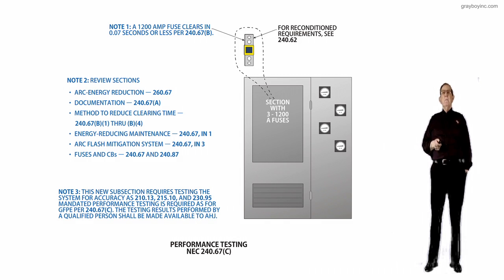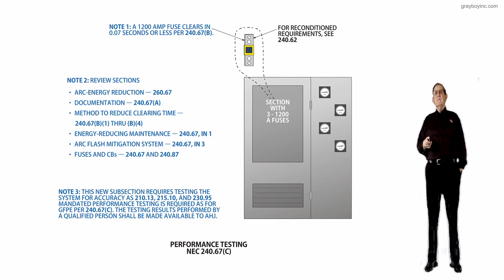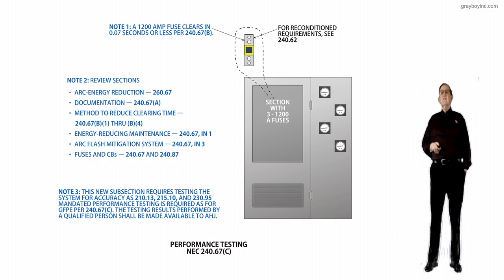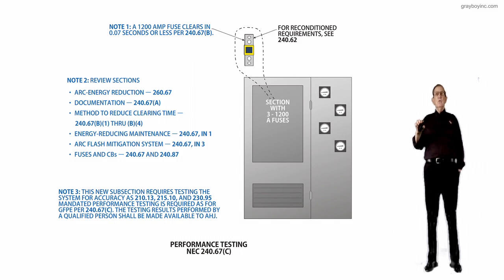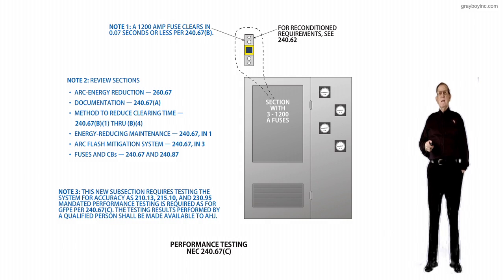B as in boy. Energy reducing maintenance that we would have listed here is 240.67 informational note 1. Arc flash mitigation systems, 240.67 informational note 3, tells you how you can reduce the amount of arc flash that could occur. And then fuses and circuit breakers. Fuses, 240.67. Circuit breakers, now we'll review 240.87.